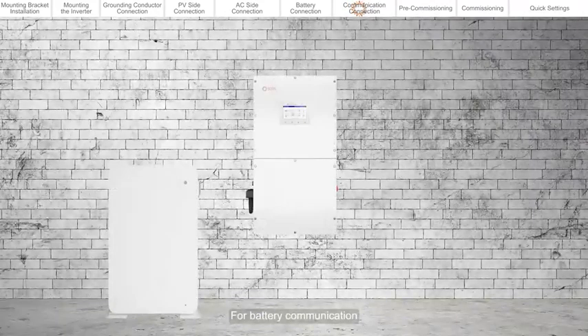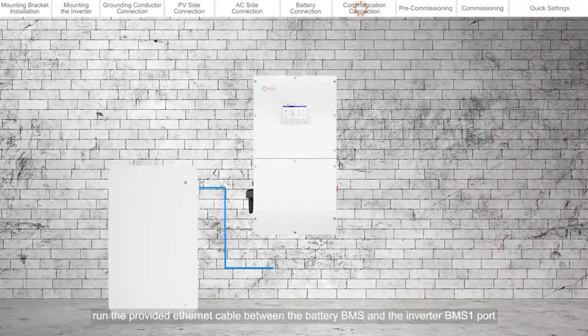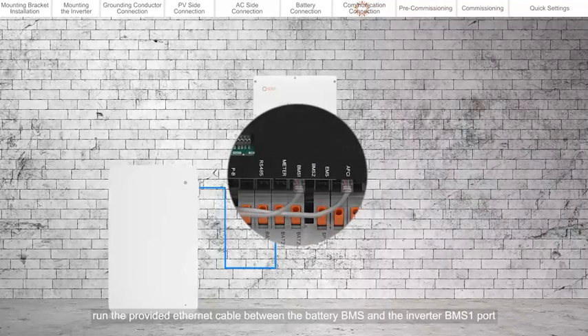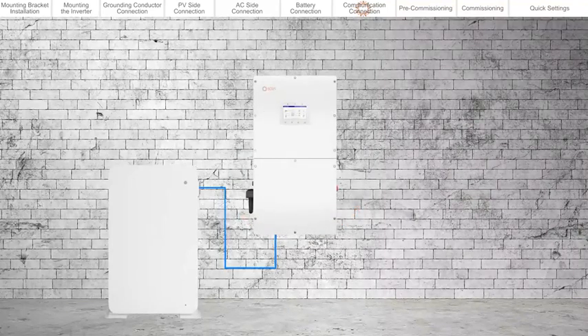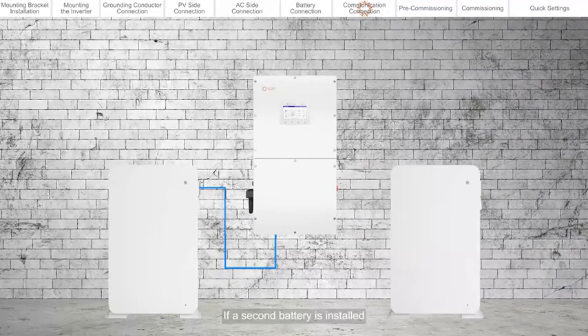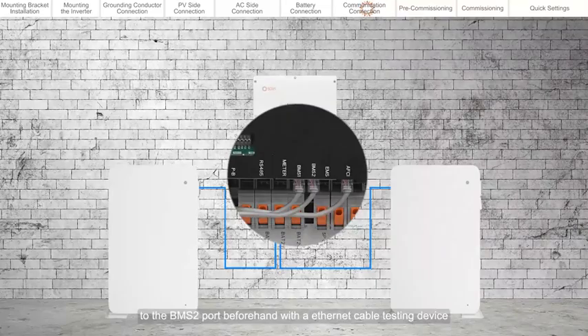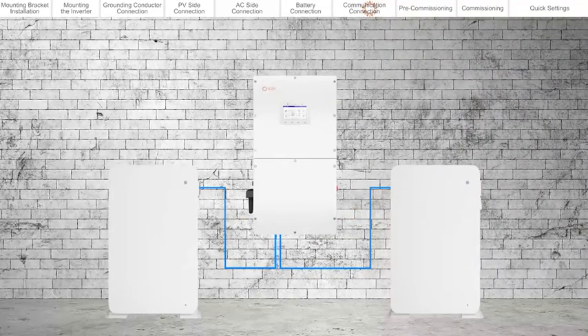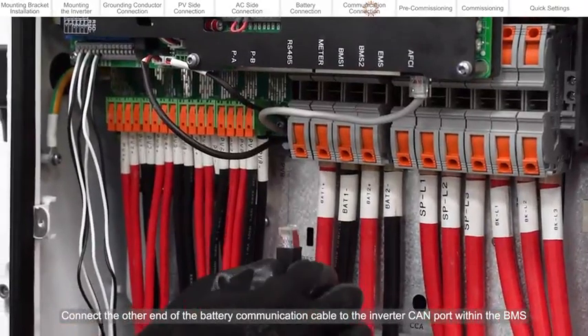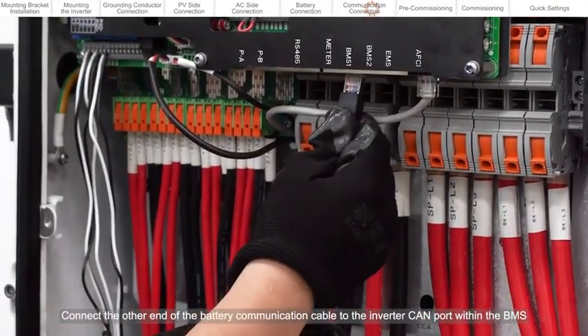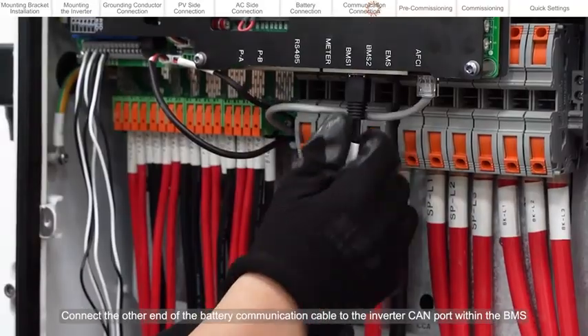For battery communication, run the provided Ethernet cable between the battery BMS and the inverter BMS1 port. If a second battery is installed, be sure to test the Ethernet cable used to connect the second battery to the BMS2 port beforehand with the Ethernet cable testing device. Connect the other end of the battery communication cable to the inverter CAN port within the BMS.